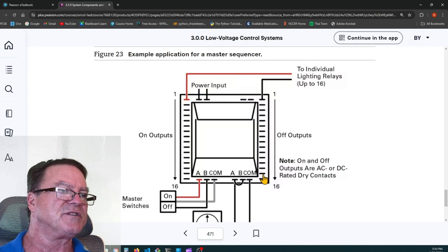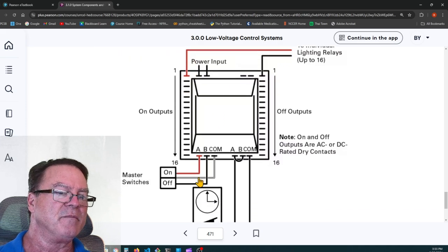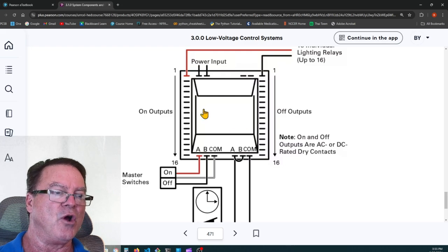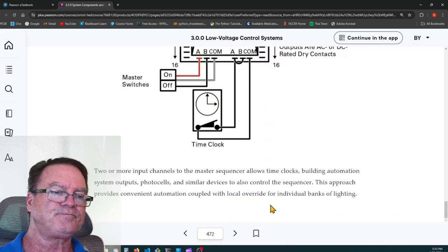Here's 1 through 16 to individual lighting relays, up to 16 of them, and one side is on, that red side is on, and the black side is off. So this master sequencer can turn all of the lights on or off at the same time, and if you come into your office, if you're working late and it turns all the lights out, you can just turn your lights on, and you can override this master sequencer without turning on every light in the building.